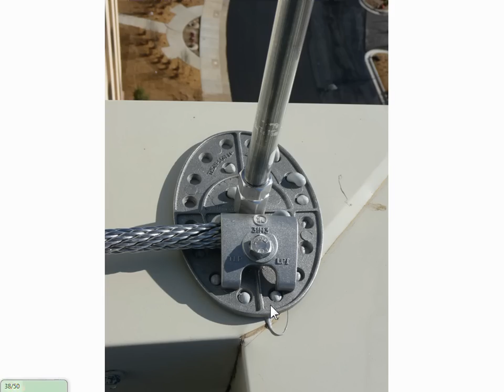It's very important. Air terminals must be spaced every 20 feet on the outside of a building, and they must be within 2 feet of the outside edge. When you place your air terminals on your building, you start on the corners and then work your way in between every 20 feet. Even on a flat area of the main roof, those air terminals are spaced every 50 feet. Any on the perimeter, correct? Or you know, 20 feet around the perimeter, 50 feet around the inside of the building. When you look in this packet, there are actually little diagrams of where they need to be placed.